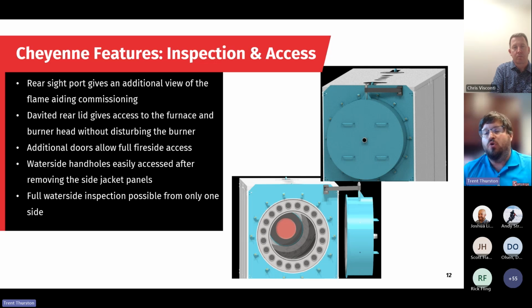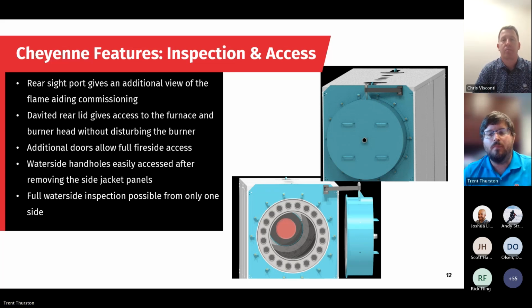The other thing with that door being able to open is we can access the furnace and burner head without removing the burner. In several other competitors, they'd have to remove the burner to work on it or to inspect the furnace. And this requires removing the gas train and several other steps that are not needed with the Cheyenne boiler. We do have fire side access at the front and back on both top and bottom vessel. And as I mentioned, those 8 handholes can allow for water side inspection from only one side.